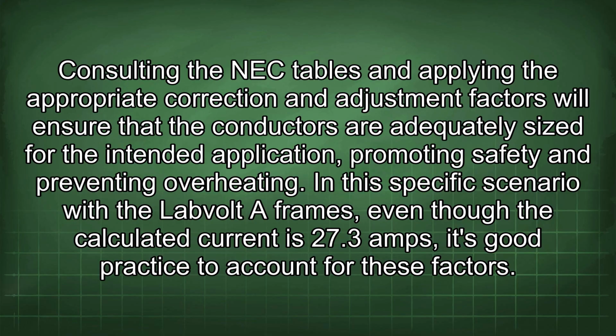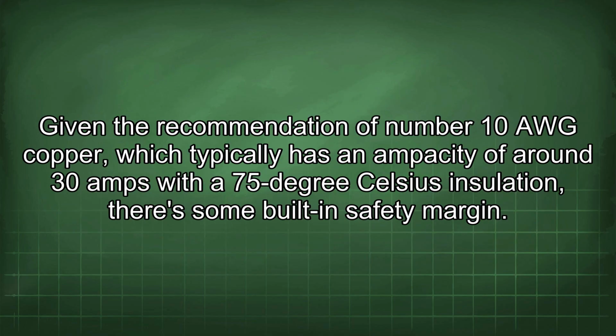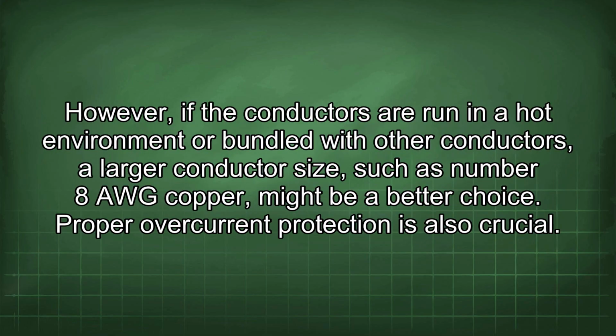In this specific scenario, with the Labvolt A frames, even though the calculated current is 27.3 amps, it's good practice to account for these factors. Given the recommendation of number 10 AWG copper, which typically has an ampacity of around 30 amps with a 75 degrees Celsius insulation, there is some built-in safety margin. However, if the conductors are run in a hot environment or bundled with other conductors, a larger conductor size, such as number 8 AWG copper, might be a better choice.